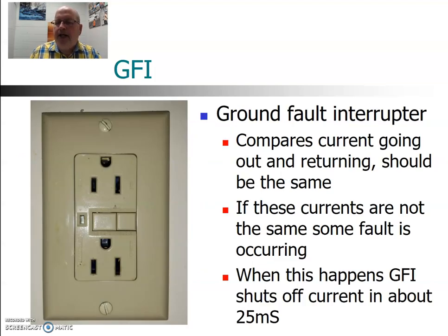Here's a device that can minimize the effect of electrical shock: the ground fault interrupter, or GFI. It compares the amount of current leaving a receptacle to the amount coming back on the neutral—those two currents should be the same. In the event of a fault there'll be a difference, and when that happens the GFI will shut off the current in about 25 milliseconds.